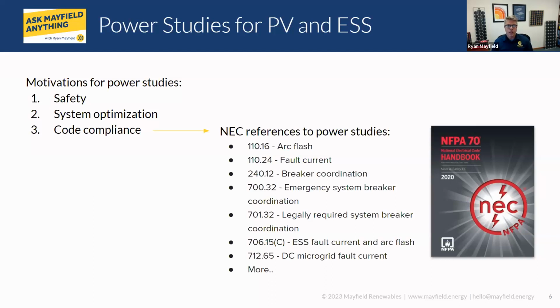And then we have a whole bunch of code references here. So for those of you that know me, code is my happy place. But you can see here, there's a number of different locations where arc flash, fault current, coordination studies, all these things show up within code. And even in chapters 1 and 2, we have requirements in 110, we have requirements in 240. So this isn't necessarily something that's new. I would say it's something that hasn't been applied within the PV industry as much as it should be, but we're definitely starting to see that change.